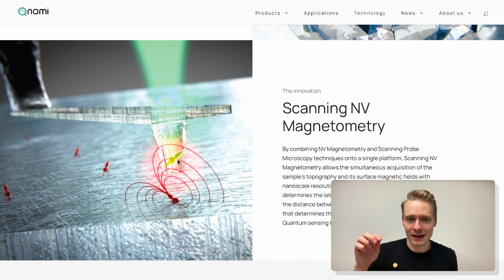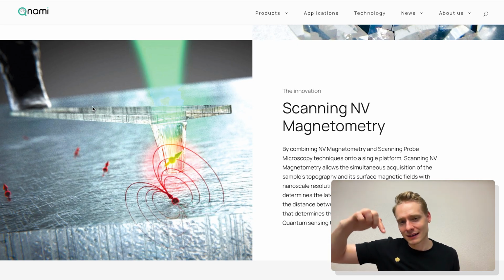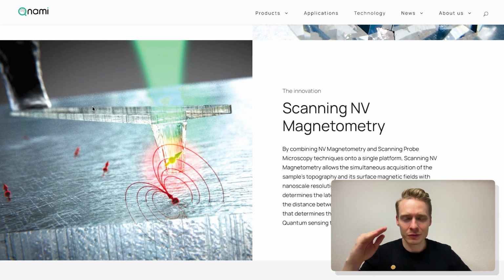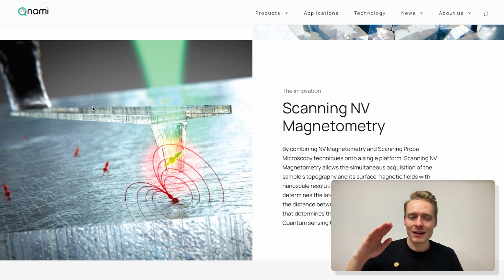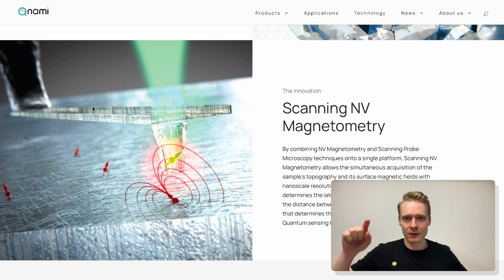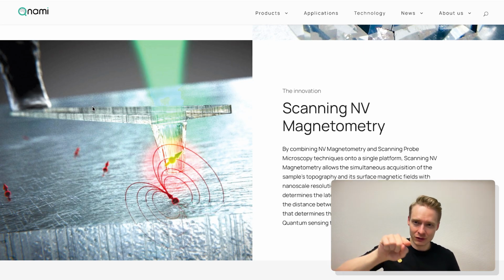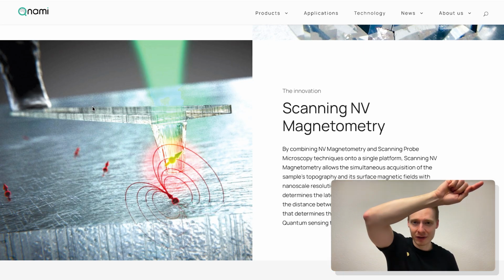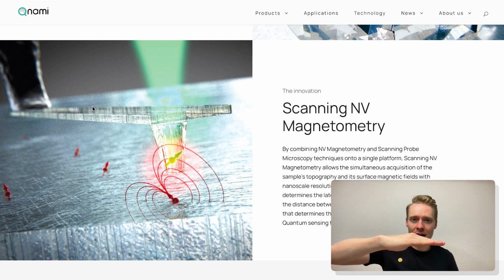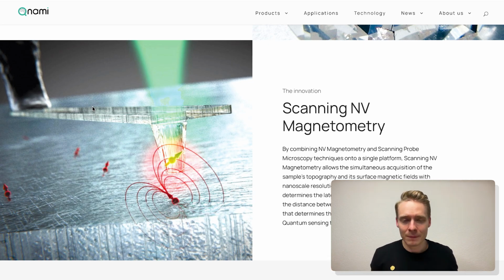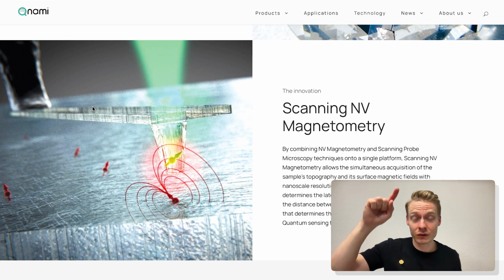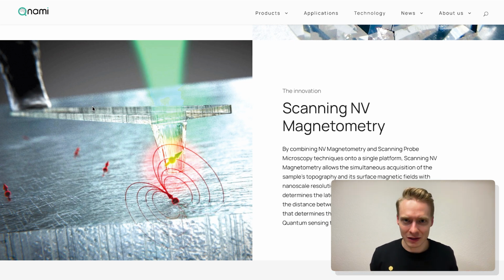And then you're using a laser to shine on this cantilever, like shown here in this illustration. So you're shining the light at an angle, and a very tiny movement of this lever creates a movement of this laser beam on a projected surface. So if you had the laser beam coming in from this direction, being reflected from the lever and going up in the other direction, and now you're bending the lever a little bit, then of course you get a leverage effect on the trajectory of your laser beam, and that's how you're measuring this.